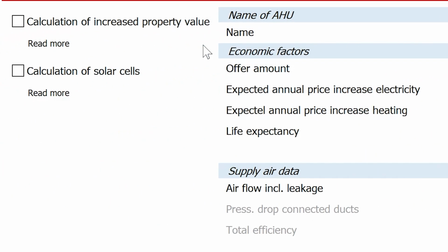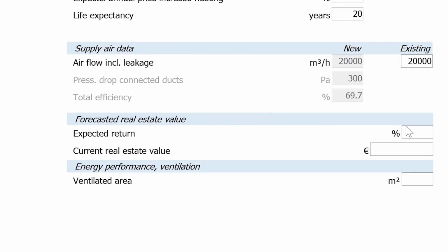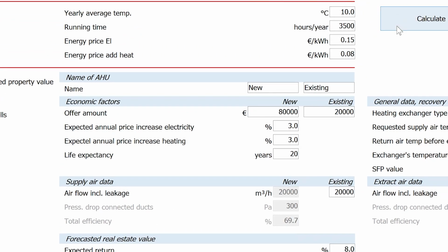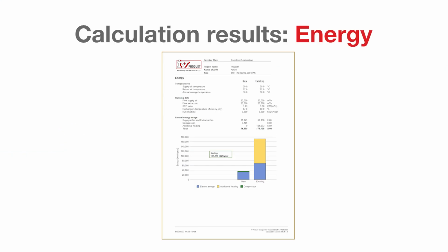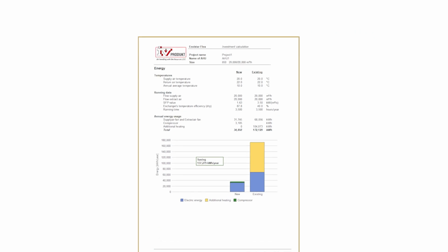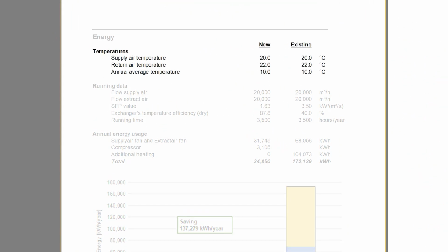We also take the opportunity to calculate how the property value will be affected. Here we will fill in the expected return. And if we know the ventilated area, we can enter it here. Now let's calculate. Here we can see the temperatures and airflows. The SFP value is reduced from 3.5 to 1.63. The temperature efficiency increases from 40 to 87.8%. The rotary heat exchanger is at 82.6%, but together with the heat pump in Thermocooler HP, the total is 87.8%.